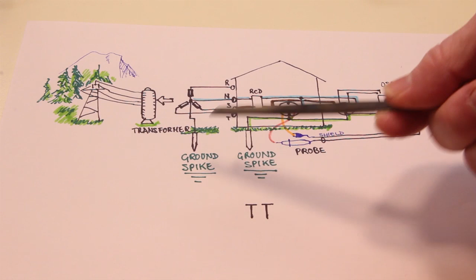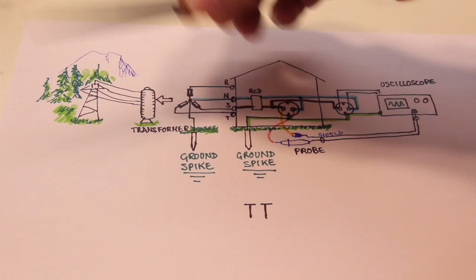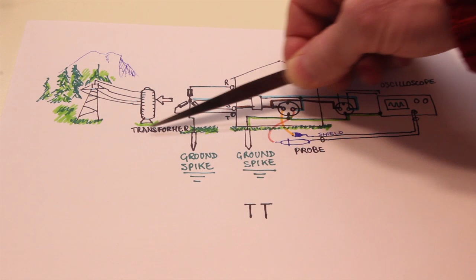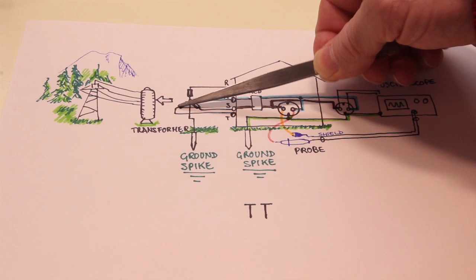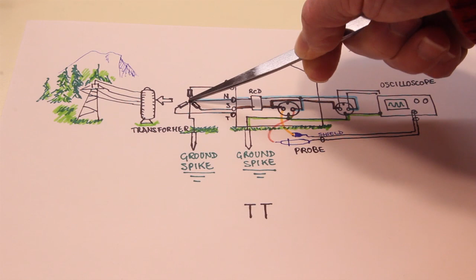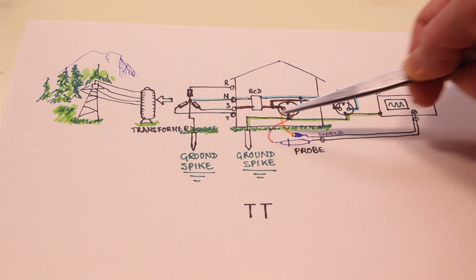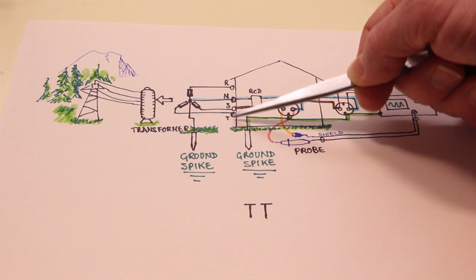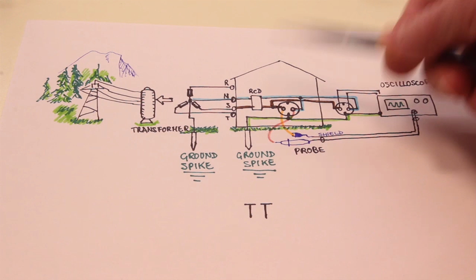This is a TT system, but even with the TN system the problem is similar. We have the line that comes from the power station and arrives at a local transformer, usually connected star or Y, where the center is grounded through a spike into the ground, and the three phases are provided to the user—maybe two of the three, or all three, depending on the contract you have with the utility company.